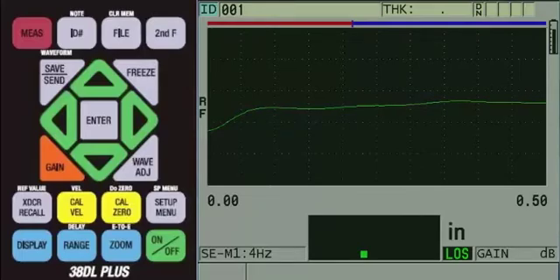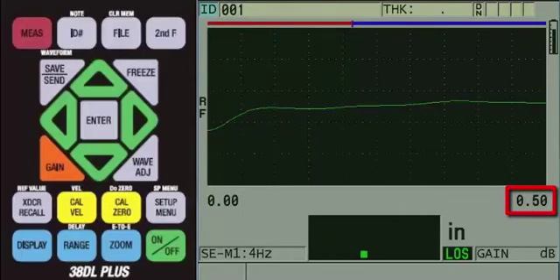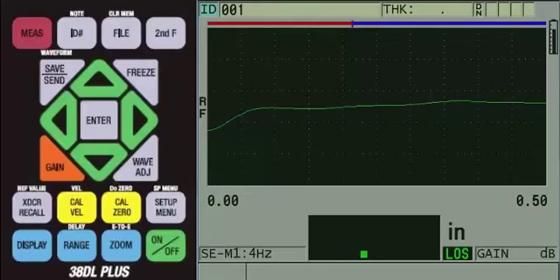Currently, the range is set to half an inch. If you are using metric units, it will be set to 10 millimeters. Given the thickness of our sample, we will not be able to see the back wall echoes on screen since the range is currently set too low.